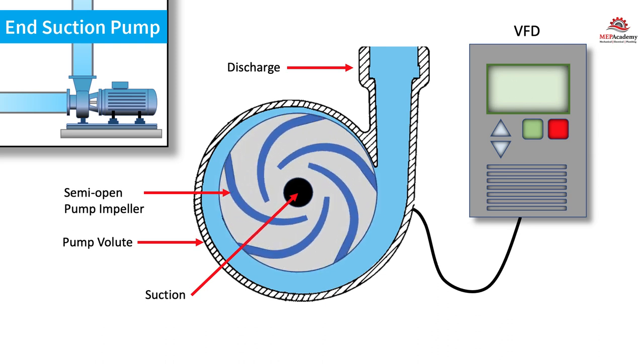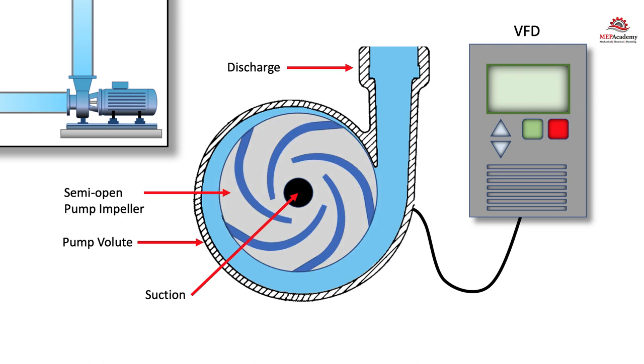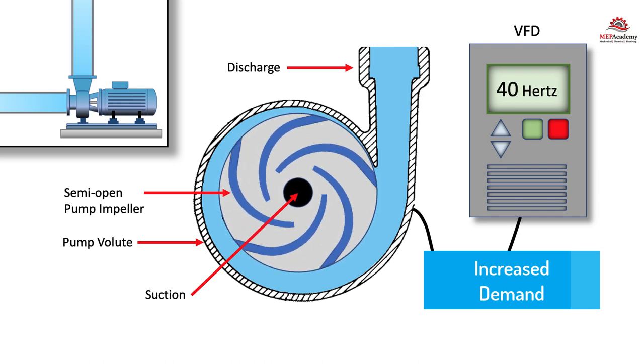The VFD will control flow based on something like a differential pressure controller sending a signal to the VFD to speed up to 40 hertz or whatever number, because the demand on the system has grown and they need more GPM.